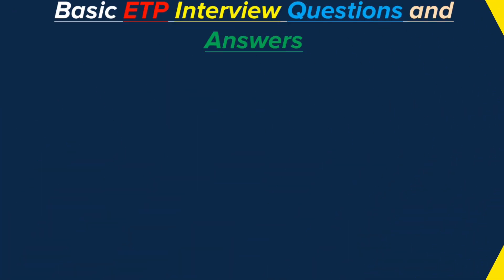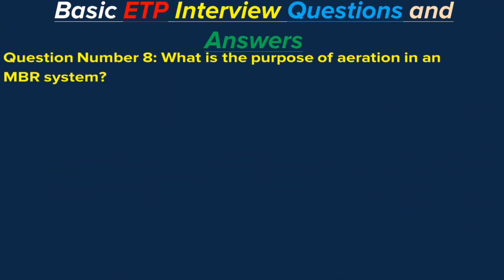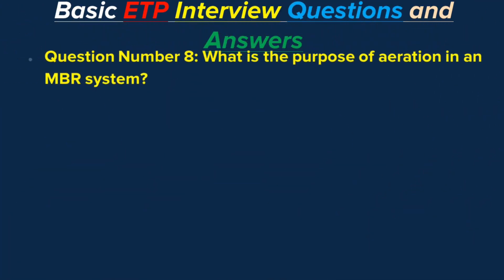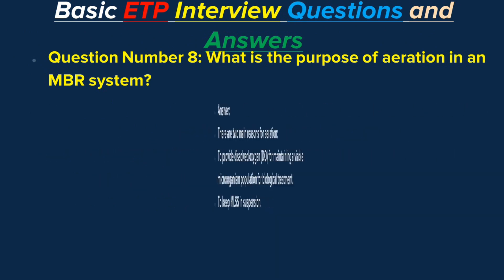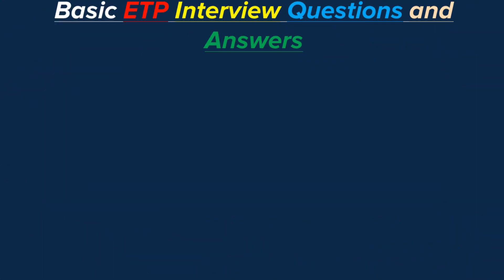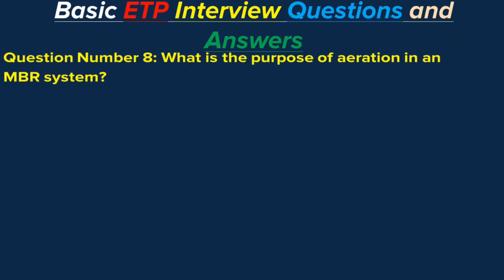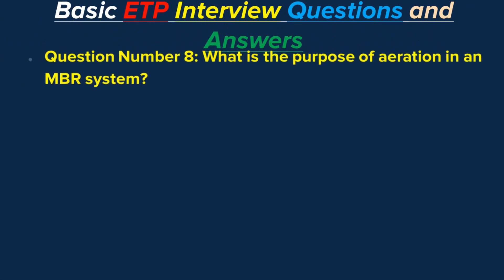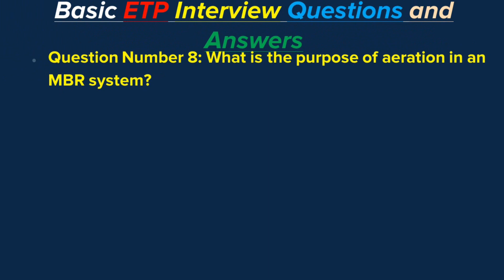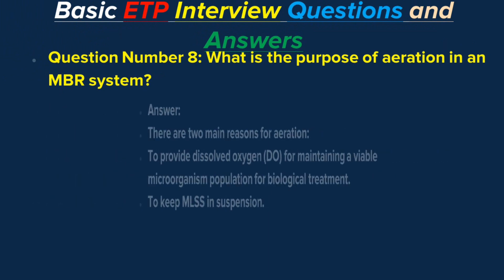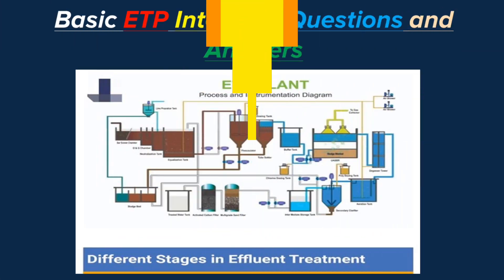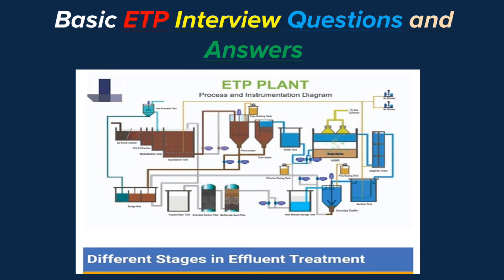Question number 8: What is the purpose of aeration in an MBR system? Answer. There are two main reasons for aeration: first, to provide dissolved oxygen for maintaining a viable microorganism population for biological treatment; and second, to keep MLSS in suspension.